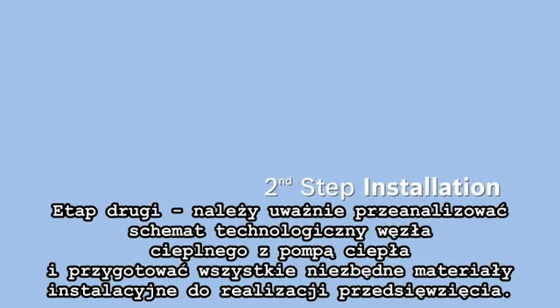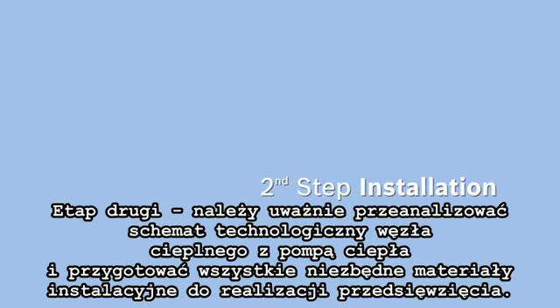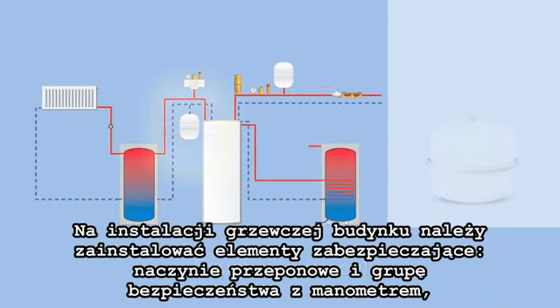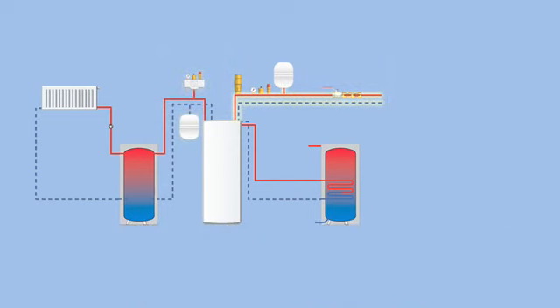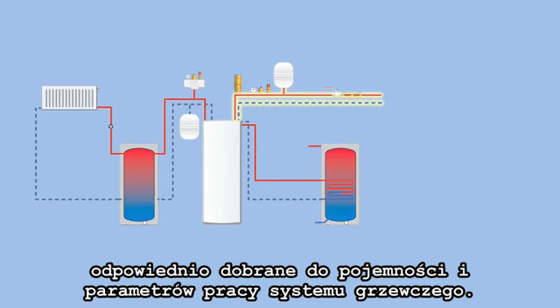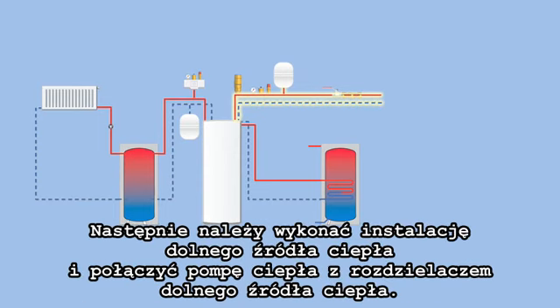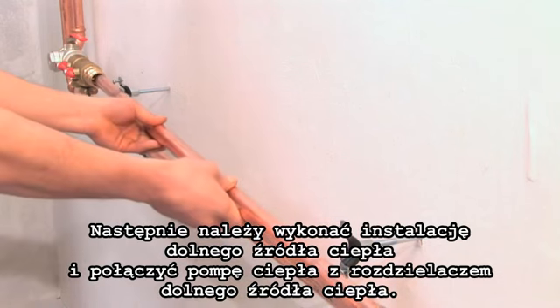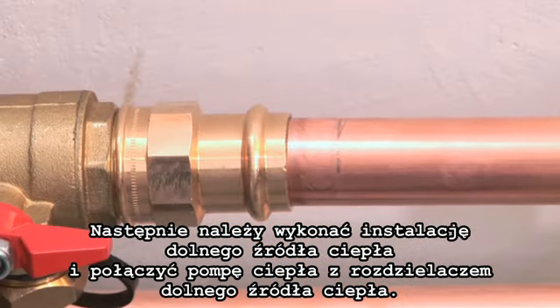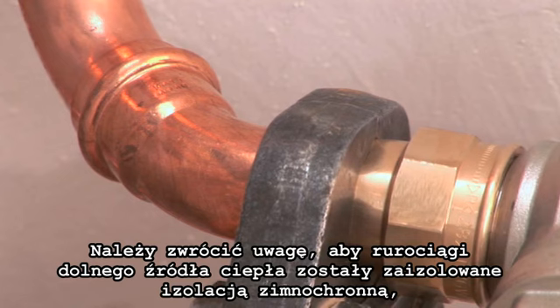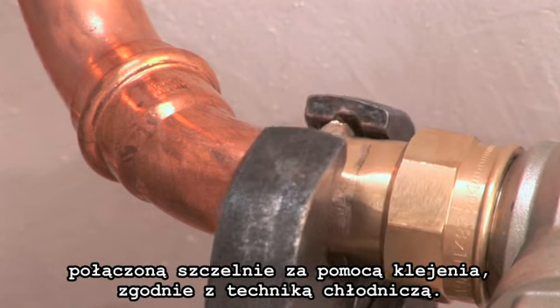In the second step, important preparations must be made in the heating circuit and the feeder lines. Please install the expansion vessel and a safety module with pressure gauge in the heating circuit corresponding to the volume of the heating system. Now connect the pipes for the heat source side and link it to the geothermal heat probe at the brine distributor. The connections are sealed as usual and insulated against the cold.